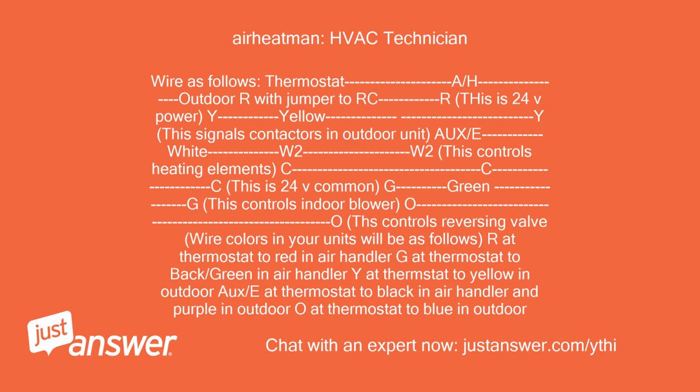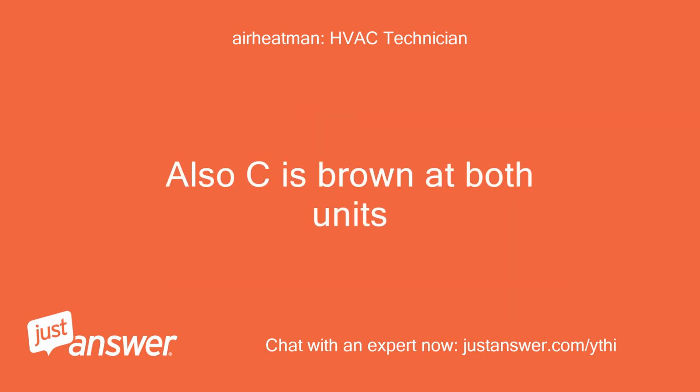Wire colors in your units will be as follows: R at thermostat to red in air handler, G at thermostat to green in air handler, Y at thermostat to yellow in outdoor, Aux/E at thermostat to black in air handler, and purple in outdoor, O at thermostat to blue in outdoor. Also C is brown at both units.